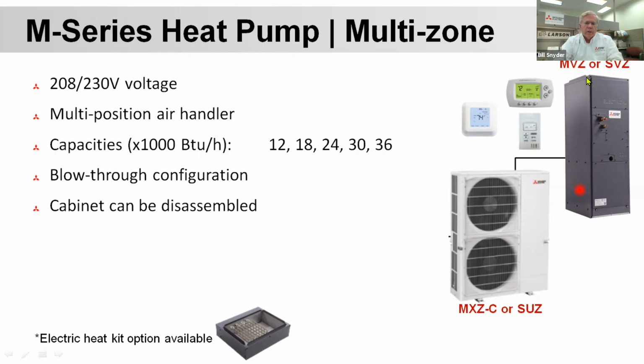It's multi-position: upflow, downflow, horizontal left and horizontal right. It's available in a 1 ton all the way up through 36,000 BTUs. It has an optional electric heater you can throw on the top. And I've had people put hot water coils on these as well. Again, a third-party coil will go on there, and we just open and close the zone valve if we need to. It is a push through. The blower's in the bottom. The coil sits in here. So it pushes through the coil. The condensate drain is pressurized on this unit. This is the only unit that it is.